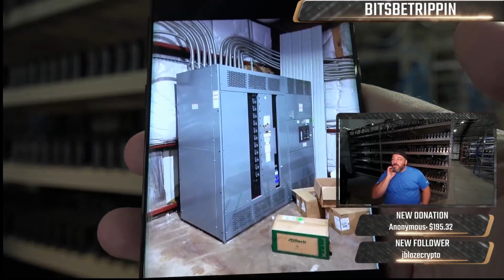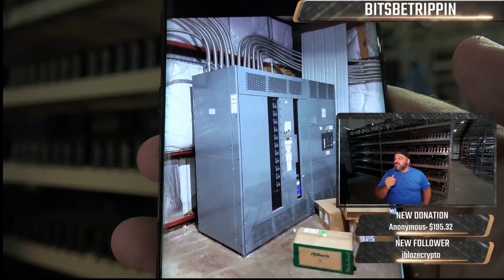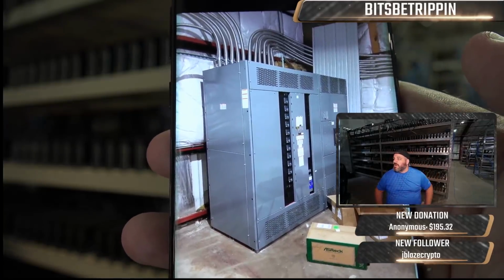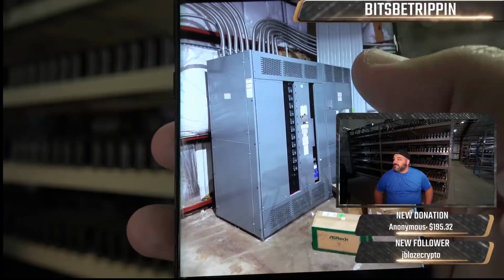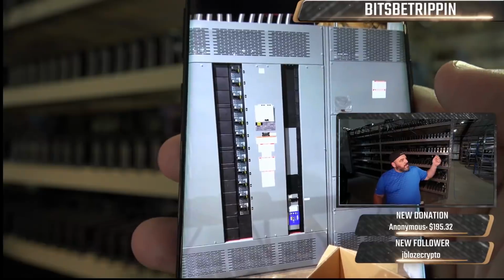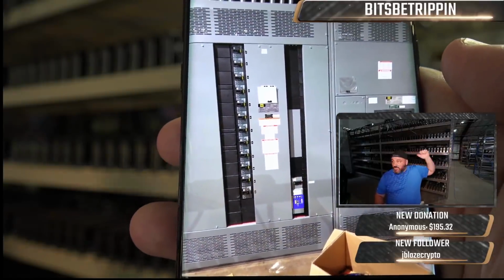So that's the main power distribution block. That's 3,000 amp service, about 2,000 being used, and you can see the piping that we have to go. Each of them goes to a separate call out box there, but that is the power box there. And then each one of those is what, a 30 amp connection? Or no, that's a 200 amp. 200 amp, over to the 30 amp breakouts.